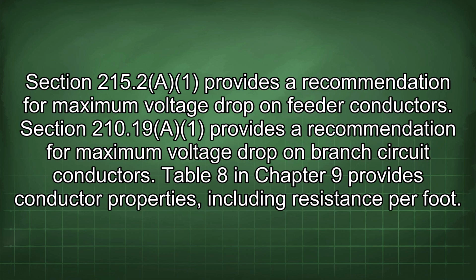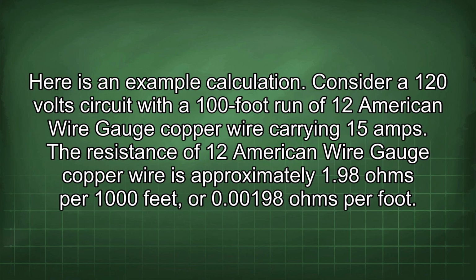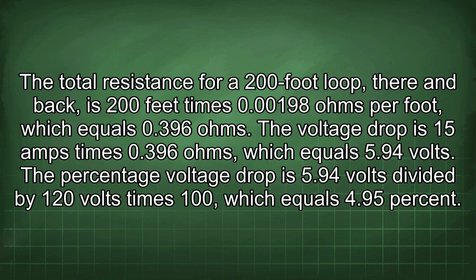Table 8 in Chapter 9 provides conductor properties, including resistance per foot. Here is an example calculation. Consider a 120 volt circuit with a 100-foot run of 12 American wire gauge copper wire carrying 15 amps. The resistance of 12 American wire gauge copper wire is approximately 1.98 ohms per 1000 feet, or 0.00198 ohms per foot. The total resistance for a 200-foot loop, there and back, is 200 feet times 0.00198 ohms per foot, which equals 0.396 ohms. The voltage drop is 15 amps times 0.396 ohms, which equals 5.94 volts. The percentage voltage drop is 5.94 volts divided by 120 volts times 100, which equals 4.95%.